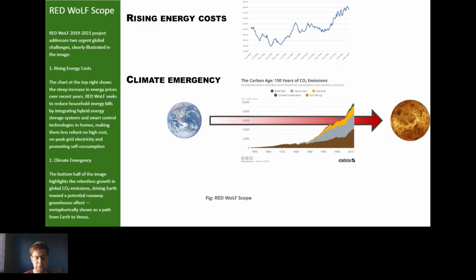The Red Wolf project piloted about 90 buildings with different LCT technologies, which are smart controlled and all connected together to external signals. One signal was available straight away: carbon intensity, live available via API, as well as its forecast. You're able to tune the equipment inside the house to follow the signal, resulting in carbon savings that were quite big in this case, about 58 to 62%.